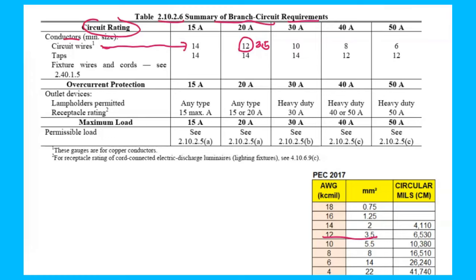And then pag 30 ampere trip daw, okay, this is square mm. Pag 30 ampere trip daw, ang circuit wires mo is dapat number 10, which is yung number 10 is itong 5.5. So let's use 5.5 square mm pag 30 ampere trip ang ginamit natin.